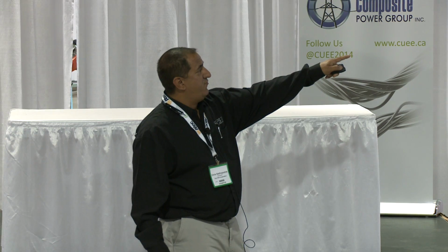Or if you have that bare concentric neutral wrapped on the outside of your cable, the cable 35, 40 years old. I don't know if cable's that old out here, but every other utility, every other company I deal with, that's typically what they say, right? You guys are nodding, so yeah, it is. If our neutral's completely gone, that's as far as we can see. So the machine really doesn't know the difference between an open or an end. All it's saying is, that's all I can see. I can only see up to that point. So what you do at this point is verify that end, or your map says, hey, my map says 800 feet to the end of the cable, we're good.